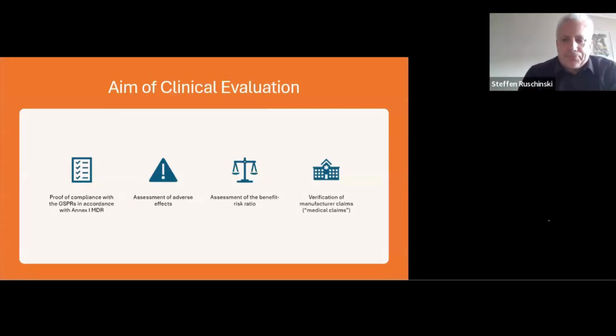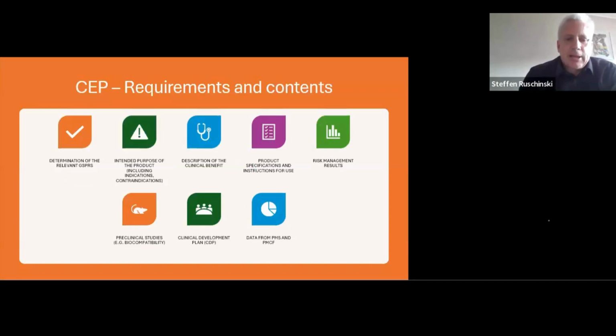So first of all, what's the aim of a clinical evaluation? We have to prove the compliance with the relevant GSPRs in accordance with Annex 1 of the MDR. We have to assess adverse effects. We have the assessment of the benefit-risk ratio. And very important, we have to verify the medical or clinical claims of the manufacturer.